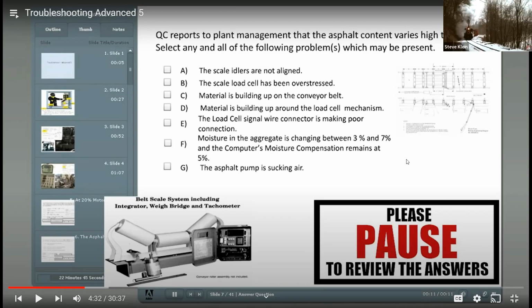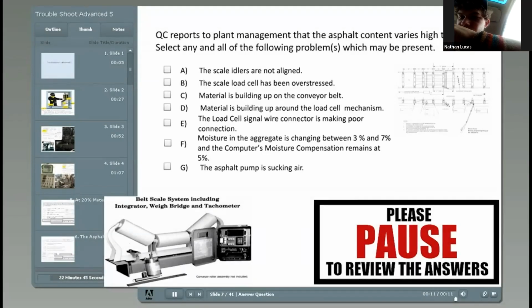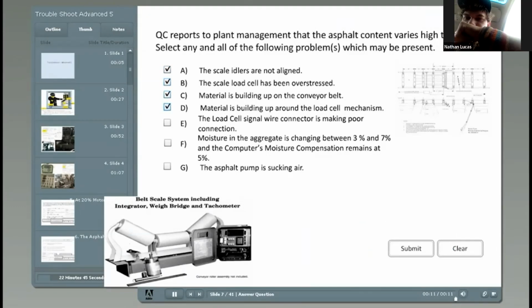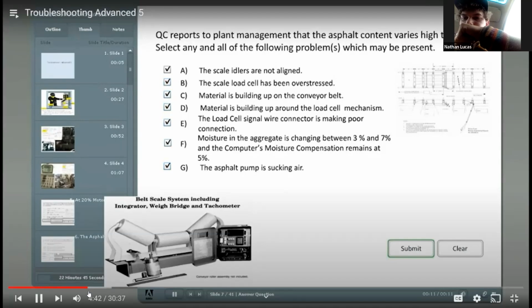Okay, how about material buildup in the conveyor belt? Yes, the mud, that changes dramatically. Yep. All right, buildup around the load cell mechanism. Yes. Load cell wire connections being poor. Could be, you could have moisture in it. Right. And moisture in the aggregate changed. Yep, I think it's all of the above. How about G, asphalt pump sucking air? Yes. I can see an argument for all of them. Right. All of the listed issues are possible causes of the problem.